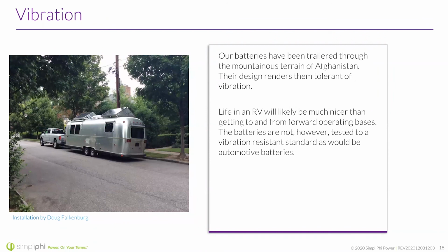Vibration. We're talking about mobile batteries. All of our batteries are rated for mobile applications. Our batteries have been trailered through the mountainous terrain of Afghanistan with the Department of Defense. Their design was basically built around that vibration, because that was a lot of our original design with the battery. Compared to life in an RV or a van, it's going to be basically nothing compared to what these batteries were designed and tested for. They're not necessarily tested to a standard for vibration resistance, but we warranted them for mobile applications. If there are any issues related to that, we can always look, but we've got a ton of batteries mobile wise, and they are all warranted for that.